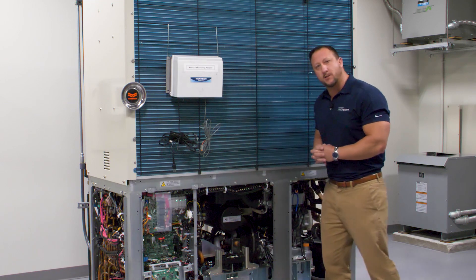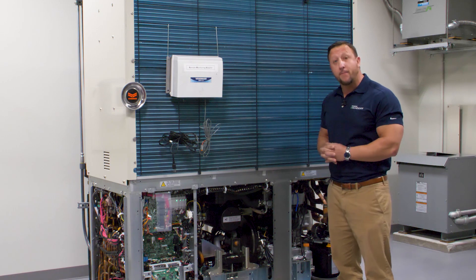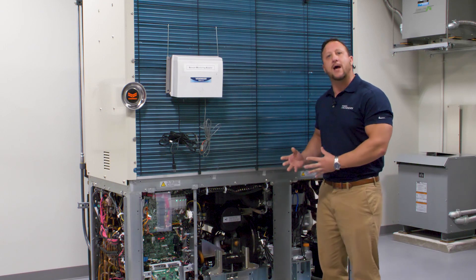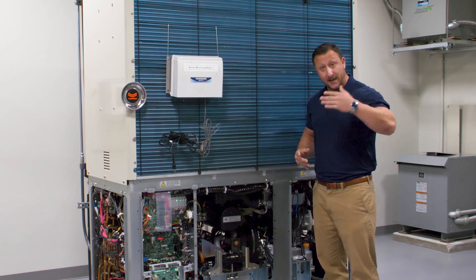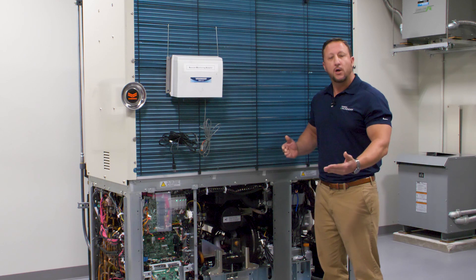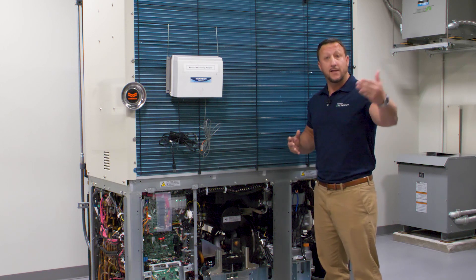Another unique feature about this system is the engine — it is a variable speed engine. The speed ranges from 650 RPM all the way up to 2,600 RPM. Coupled to that are two variable speed compressors. These compressors do not work at the same time all the time. Depending on what the demand is in the facility, the engine speed will increase and decrease, and the compressors will switch from a small compressor to a larger compressor, all the way up to a point where both compressors will be on, supplying refrigerant to the indoor units.